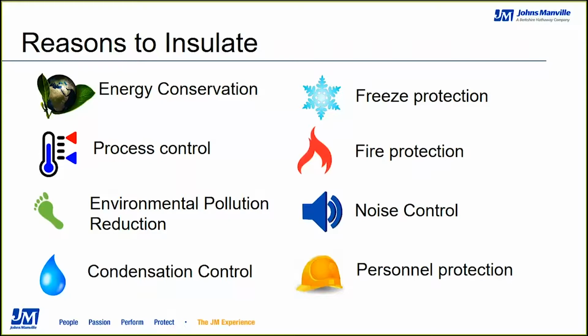While most of the reasons given so far relate to thermal qualities, mechanical insulation also carries acoustical benefits, often reducing or mitigating unwanted noise. And lastly, mechanical insulation is a key component for personnel protection. Adequate insulation will help bring surfaces that would otherwise cause severe burns down to the OSHA-approved safe-to-touch temperature of no more than 140 degrees Fahrenheit.